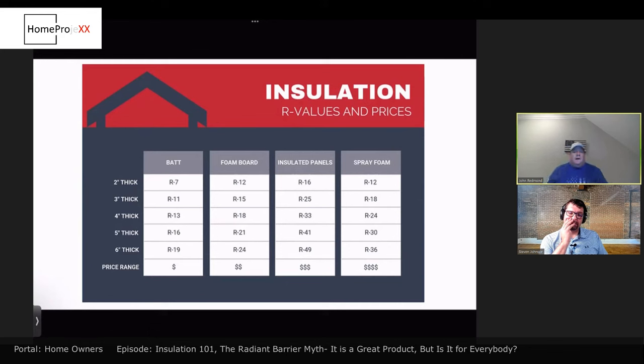So if you're trying to realize 70 degrees off of an air conditioning unit and you're blowing air that's 90 because there's 130 degree temperature in the attic, that doesn't create a very efficient heating and cooling system. It makes that system work much harder than it needs to. If you're able to reduce that delta as much as possible with the radiant barrier, it's going to have a major effect on your heating and cooling system, just in terms of the ductwork itself.